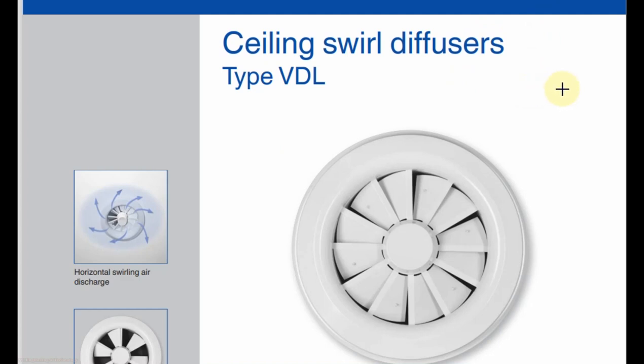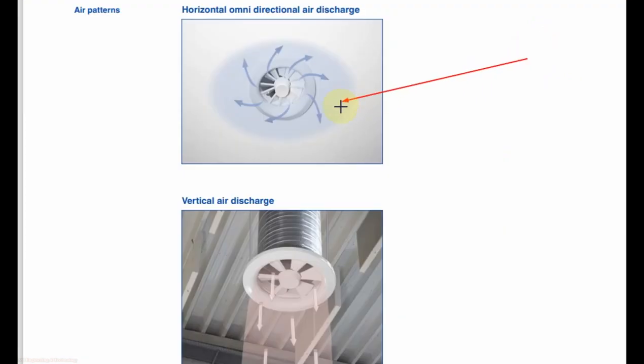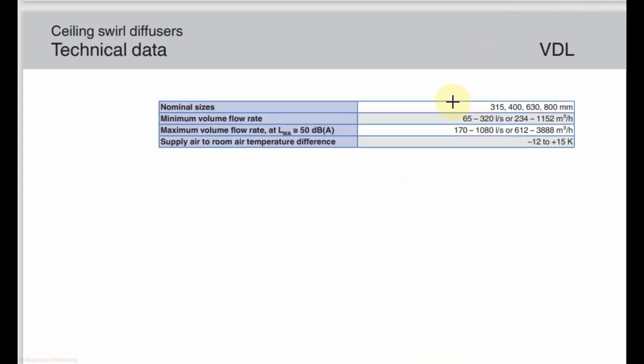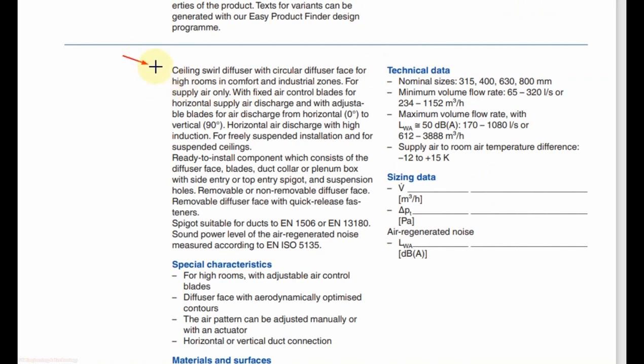Ceiling swirl diffuser is used for high areas like airports or malls. It has fixed and adjustable blades to control the air pattern. We can use it for horizontal flow pattern as well as vertical throw pattern. It can handle airflow starting from 65 liters per second up to 1080 liters per second. It comes with fixed horizontal blades and adjustable blades that can be adjusted from 0 degrees to 90 degrees vertical. You can adjust this angle as per your throw requirement.